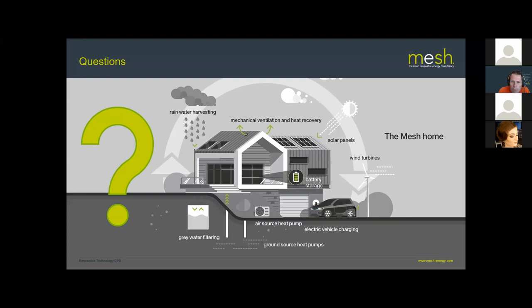Final question: can you use SAP or Passivhaus to size the heat pump system, or do you need room-by-room calculations? We always recommend room-by-room calculations. We use IES VE, building a full 3D model of the building. You can also do static heat loss calculations manually. We prefer IES because it allows us to model different systems, heat emitters, and the whole system dynamically, as well as cooling and many other analyses.